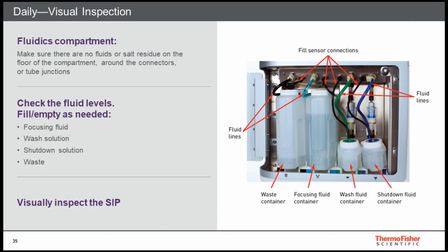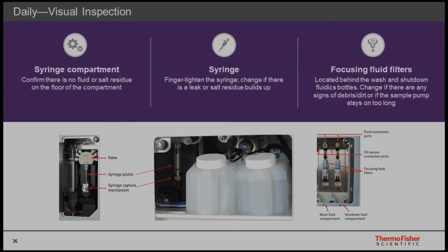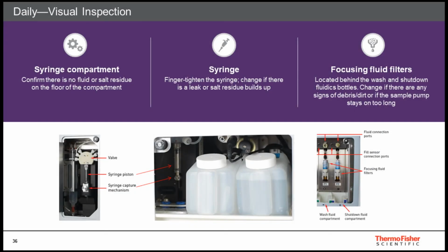Continuing on with general maintenance of Attune NxT, periodically inspect the fluidic compartment for leaks. Puddles of liquid in a flow cytometer, or for that matter any microfluidic instrument, is always a bad sign. Check the fluidic levels of all the containers and fill and empty as required. Please check the syringe and the filters to ensure there are no active leaks or signs of leaks, which can be identified by salt crystals.